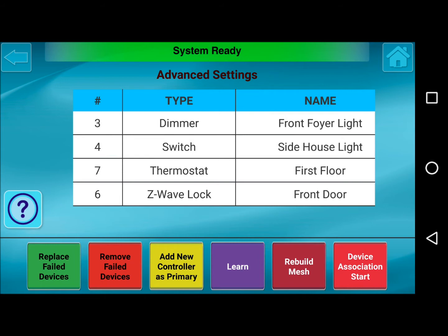Replace Failed Devices allows you to easily remove an existing failed, unplugged, or missing device. You would highlight the failed device — it has to be in a failed state because this will try to communicate to the device. If it succeeds, you would need to proceed to Remove Device. If the device has been removed from the system entirely, it will fail and then allow you to re-enroll a new device in its place.